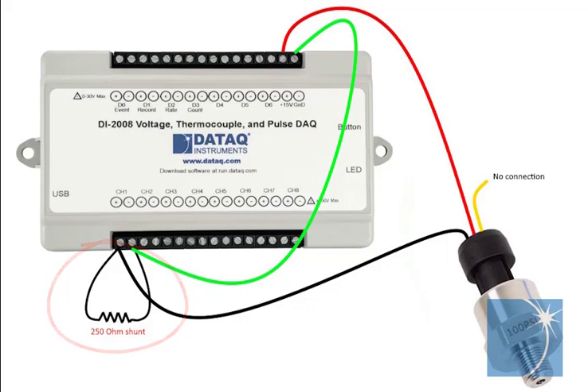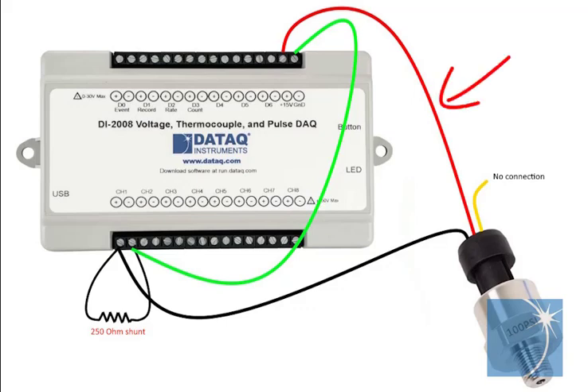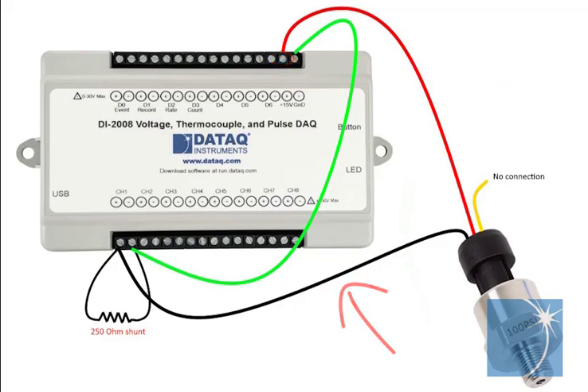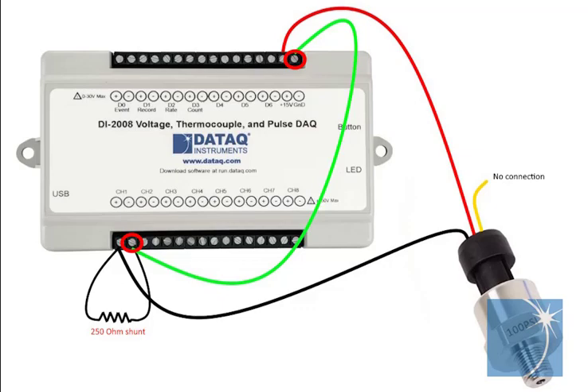The 250 ohm shunt resistor will convert the 4 to 20 milliamp output of the transmitter to a 1 to 5 volt signal that we can scale into pressure in Windac. We'll connect the red wire from the pigtail to the 15 volt supply, the black wire to the positive input on analog channel 1, and we'll run a jumper from the ground connection on the top terminal strip to the negative input on channel 1.